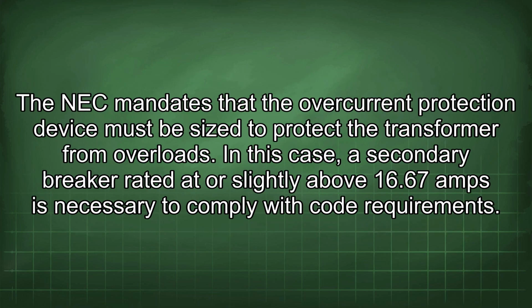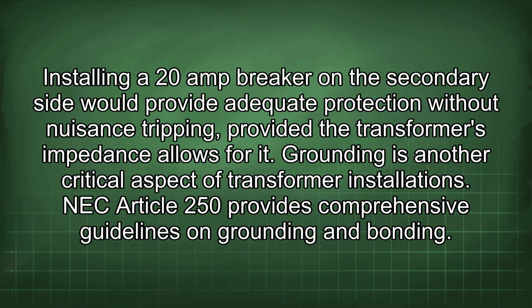The NEC mandates that the overcurrent protection device must be sized to protect the transformer from overloads. In this case, a secondary breaker rated at or slightly above 16.67 amps is necessary to comply with code requirements. Installing a 20 amp breaker on the secondary side would provide adequate protection without nuisance tripping, provided the transformer's impedance allows for it. Grounding is another critical aspect of transformer installations.